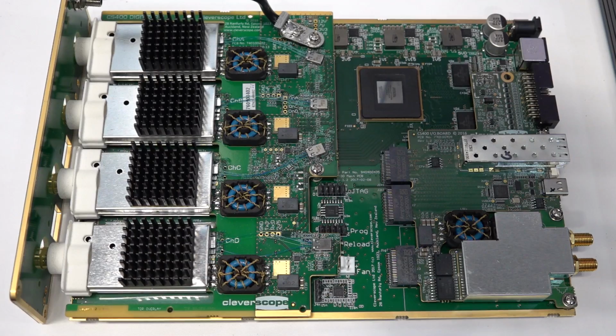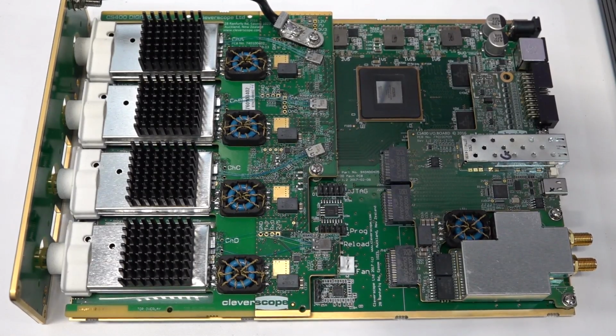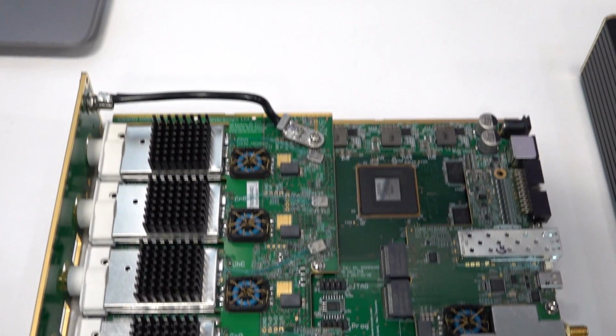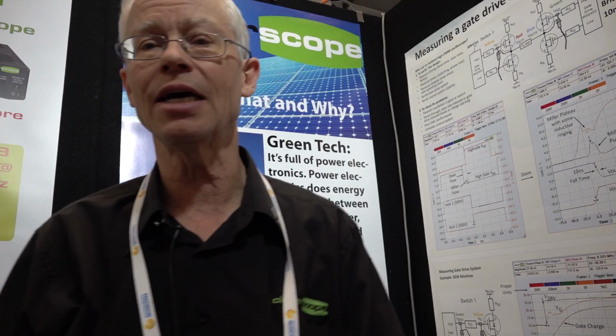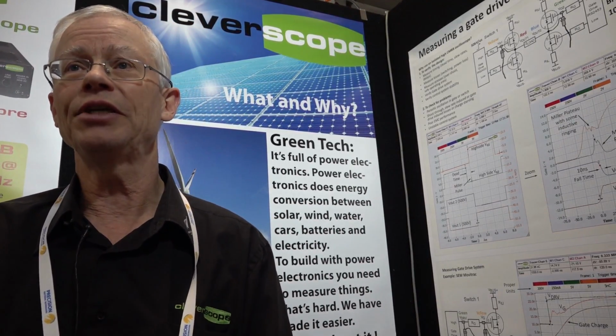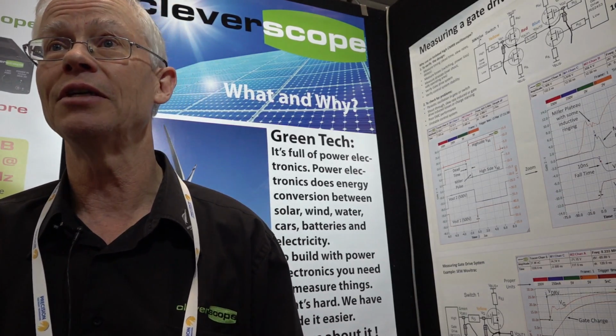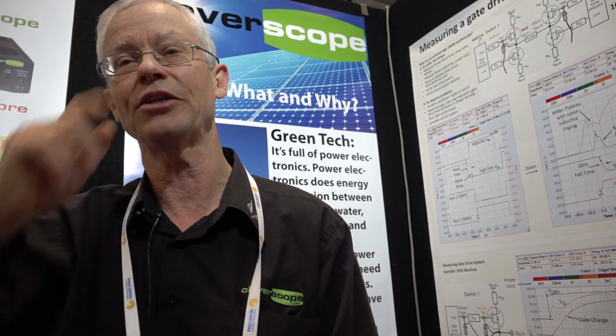Right. One of the issues is that if you've got a 14-bit converter and your channel noise is only two LSBs, like if you're looking at 800 volts, you're getting 200 millivolts of channel noise. You really want to maintain that over the entire frequency range, don't you? You do. Now, one of the big issues we have is probes. Probes themselves are not linear to that degree. They might be good for 1%, so 1 part in 100. We want 1 part in 8,000. Exactly. So that means if you're looking at a square wave, we want the top of it to be linear to within 1 part in 8,000, just 200 millivolts on 800 volts, sorry.